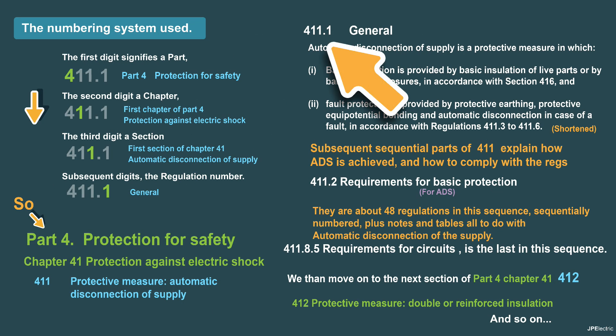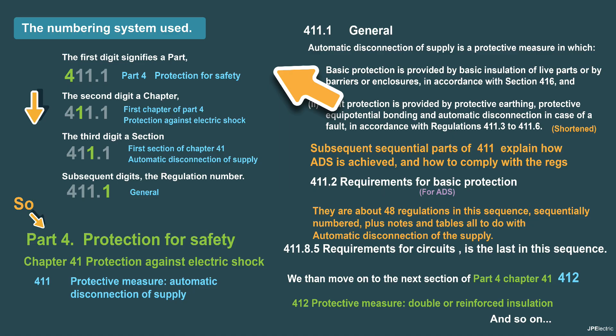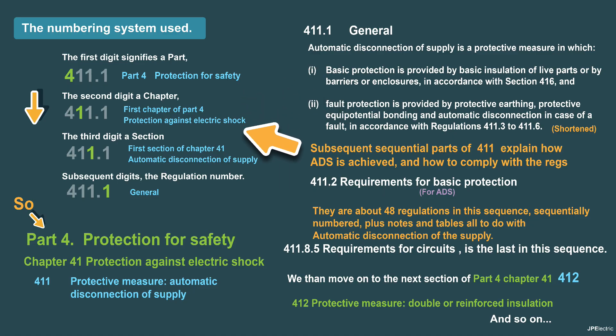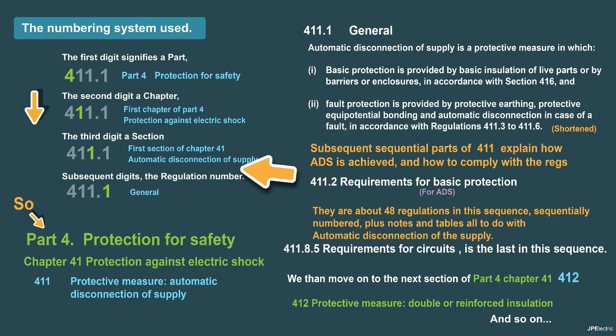So we have a regulation number: 411.1. How does that come about? The first digit signifies a part — part 4, protection for safety. The second digit is a chapter, so 41 will be the first chapter of part 4, protection against electric shock. Then the third digit, 1, will be the first section of chapter 41, automatic disconnection of supply. Then any subsequent numbers after that will be the regulation number, 411.1.